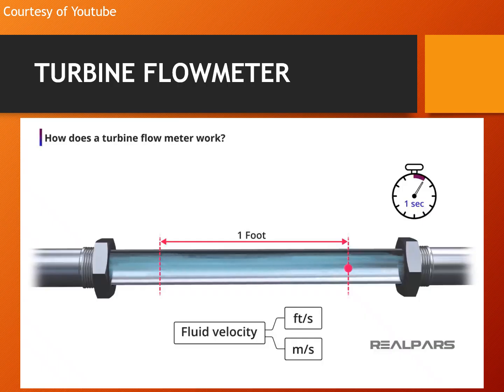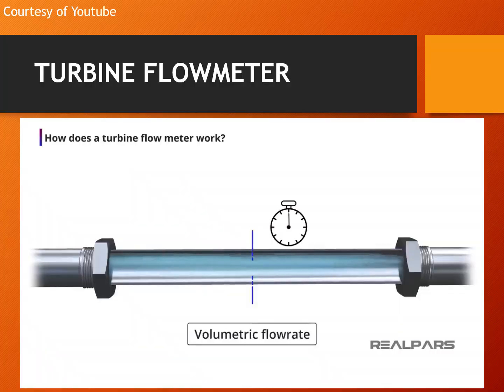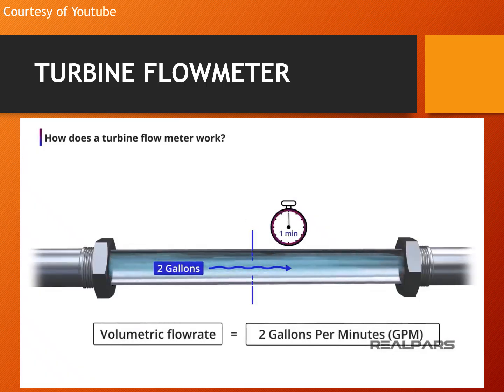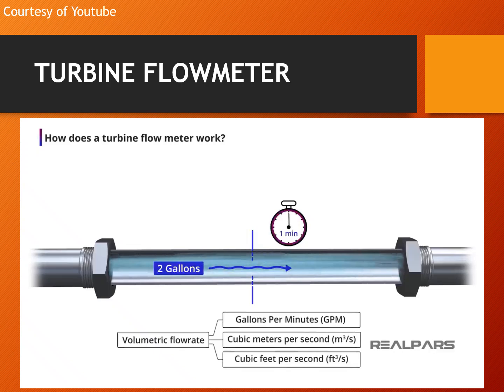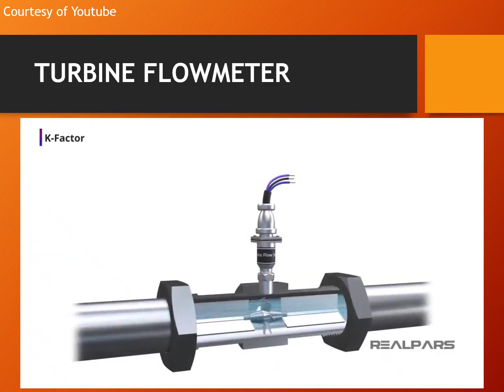Fluid velocity plays a very important role in the operation of a turbine flow meter, but in most applications, a turbine flow meter is used to measure volumetric flow rate. Volumetric flow rate indicates the volume of fluid that passes a point in a unit period of time. If you could count the number of gallons of liquid flowing past a certain point in 1 minute, you would be able to state the volumetric flow rate. Volumetric flow rate is expressed in units such as gallons per minute, or GPM, cubic meters per second, and cubic feet per second.